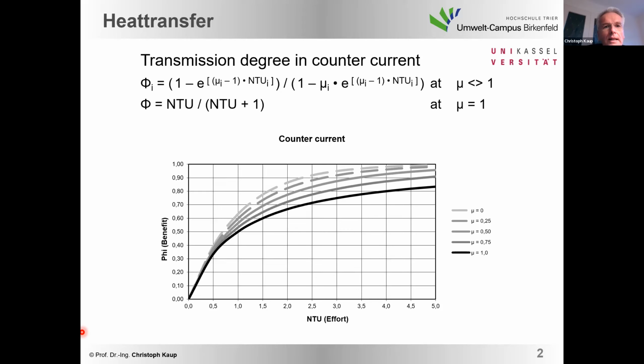on the transmission degree, or the efficiency, of heat recovery. If we would like to have a high amount of energy which we can use, then we have to use a countercurrent operation. That means, if we talk about balanced airflows, where the heat transfer capacity ratio is 1, meaning the exhaust airflow is in the same range as the supply airflow, then it's very easy to define the efficiency of the heat recovery, because it's NTU divided by NTU plus 1. So it's very easy to calculate.